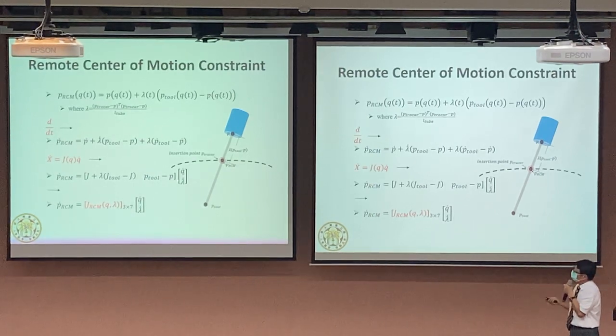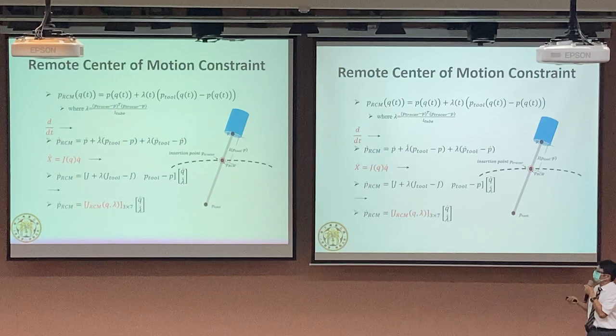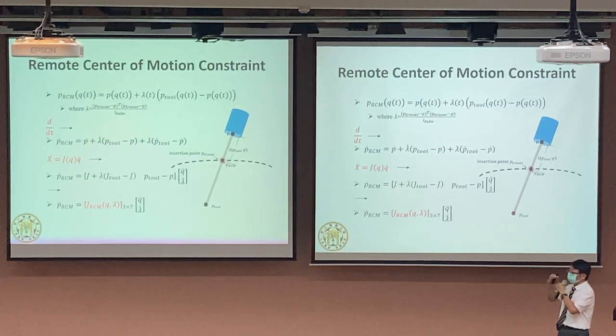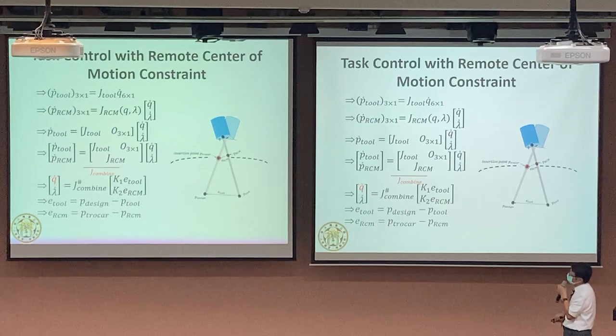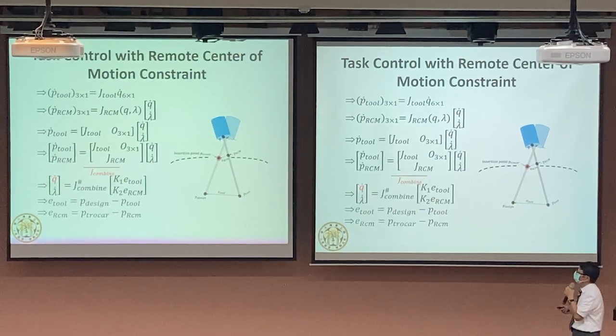Okay, so that's what we did, and what we did is using the trocar frame. For the trocar shaft, you use an additional parameter to describe the distance, the location of the trocar shaft through the patient's body, and using that we get an additional joint, an additional parameter, and we don't have to worry about the task control for remote center of motion. And I guess we're not going to go through all the other details, because what we did is we have two levels of control. One control for the robot attitude, and the other control for the distance between the shaft position and the desired remote center of motion. So that's what we get.